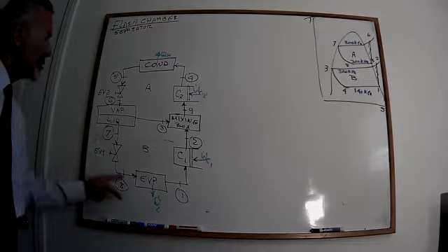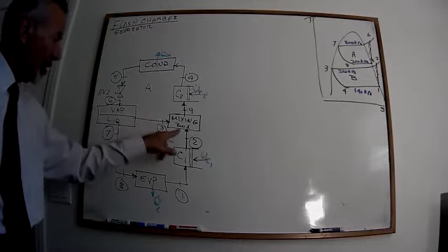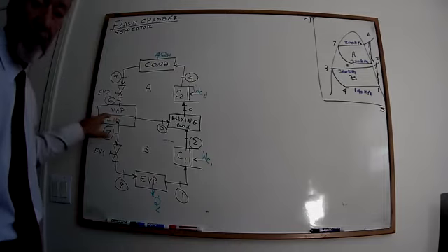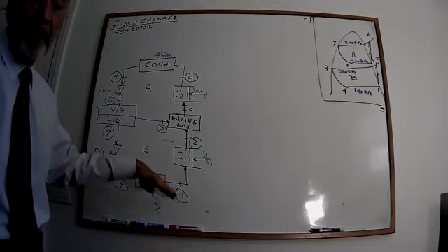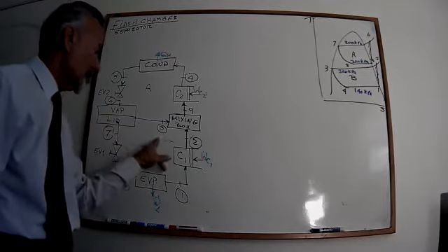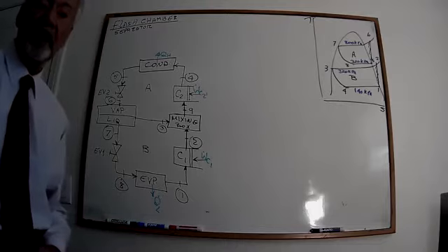So that's the problem in this cycle: this mixing box. It constantly breaks down. This is even worse, we have corrosion in it. We have a whole bunch of stuff that we constantly need to maintain and take care of. And if it doesn't work properly, it's going to ruin the compressor. So that's why we seldom use this kind of cycle, because it's just not worth doing. And the headaches of maintaining and operating it are huge.